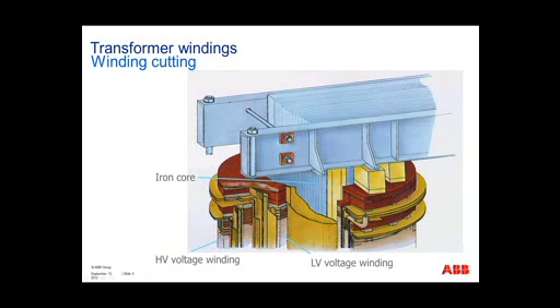Okay. The next question is, what is the significance of having phase shifting between the high voltage and low voltage winding? The benefits are you're able to isolate zero sequence contributions from one side to another if you're using a Y or a Delta connection. The other added bonus, if you have a Y-Delta connected transformer, is that you don't have to use as much copper to create the turns ratio that's desired.